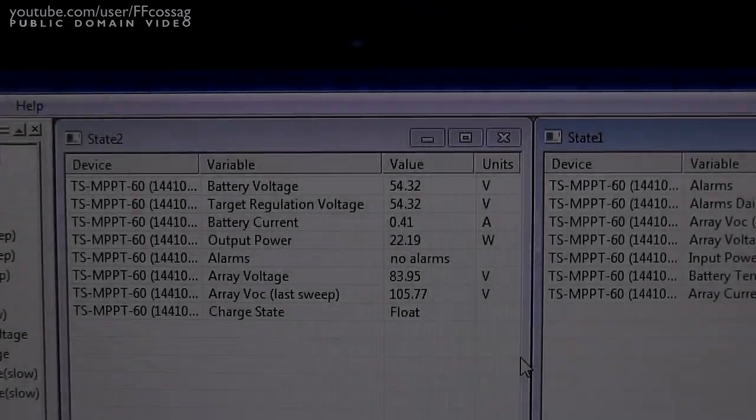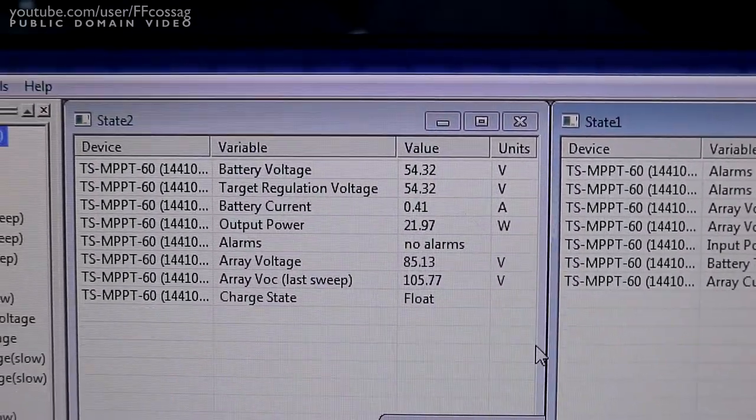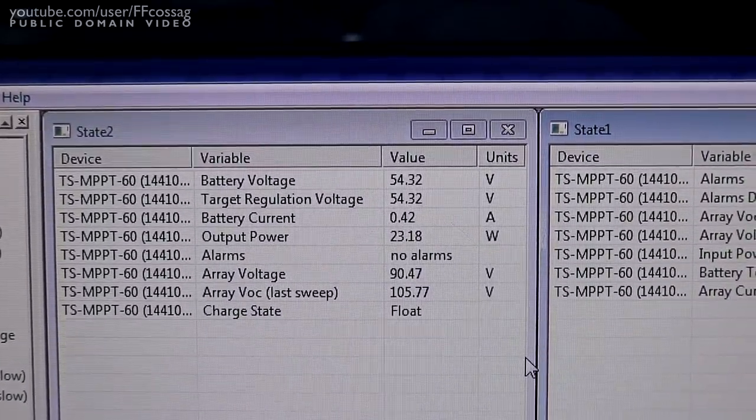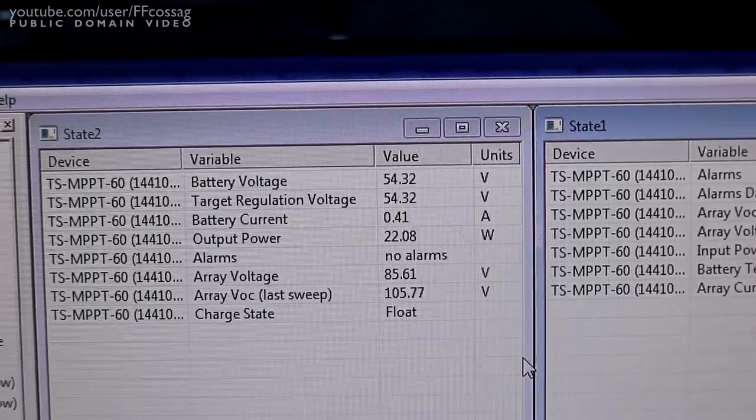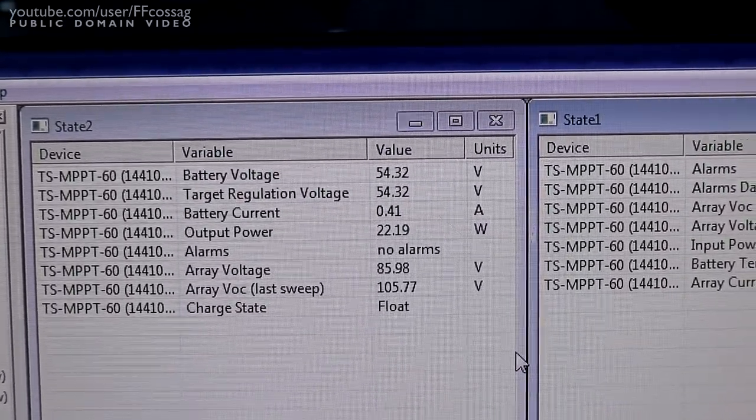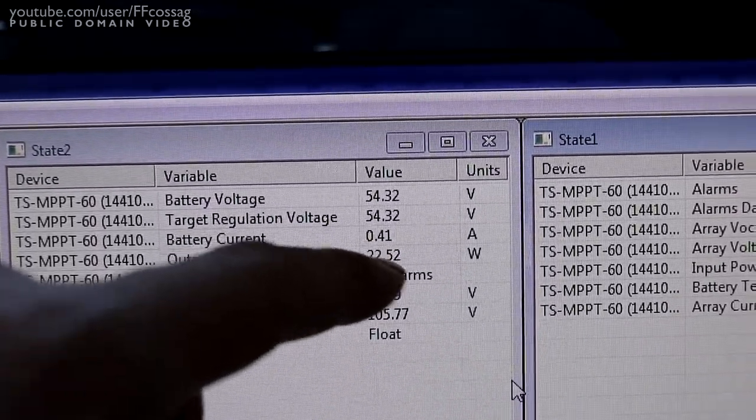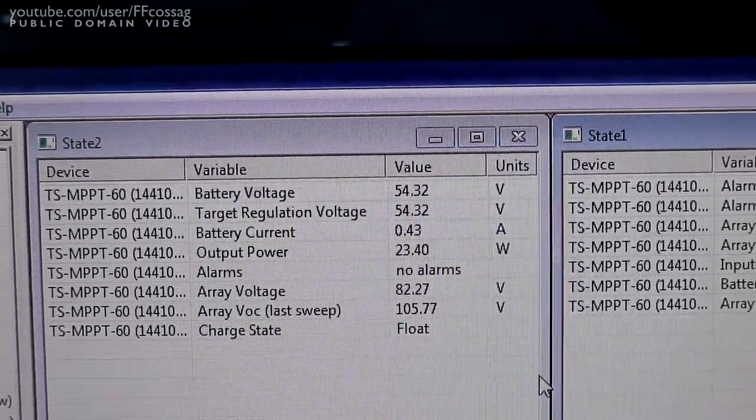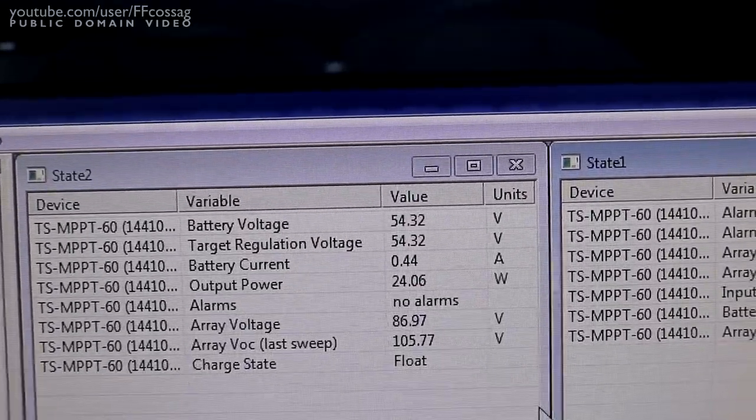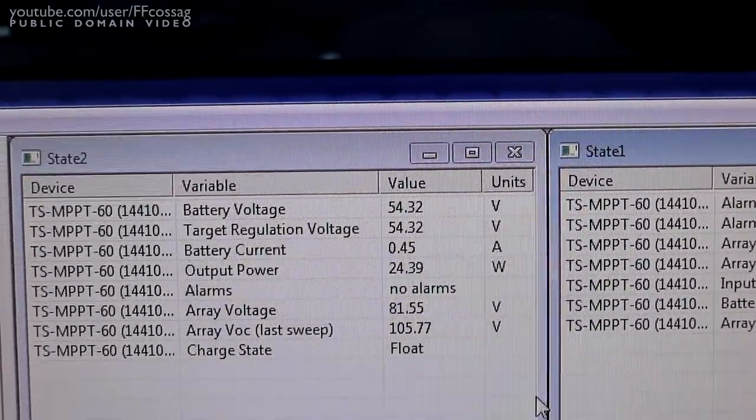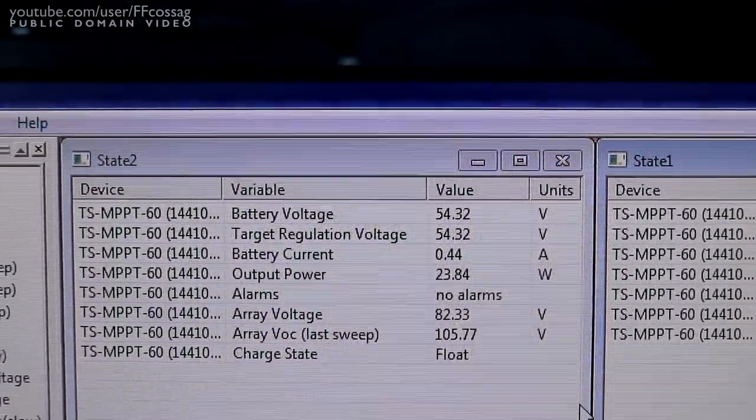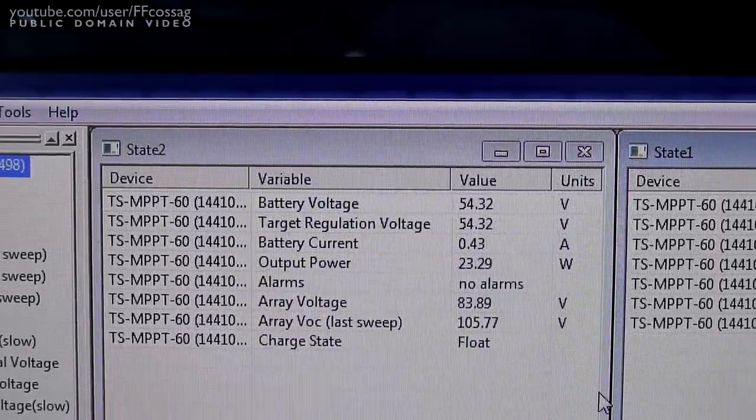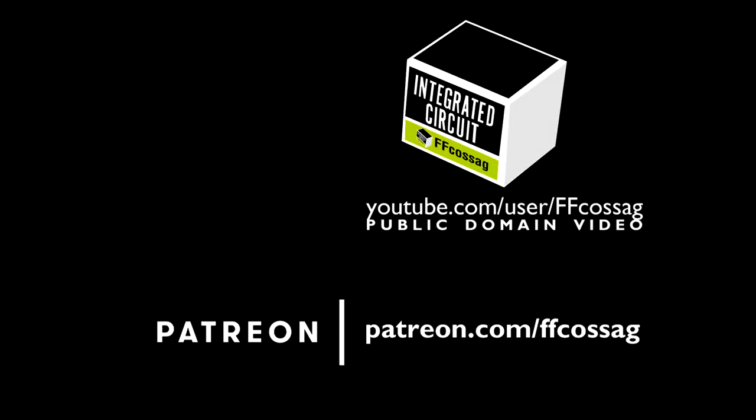Something that just keeps impressing me with these SunXtender gel cell batteries is we have 1,500 amp-hours of 10-year-old lead-acid batteries in the basement. And what's our float charge current? About 400mA. That's also about 100mA going into powering Wi-Fi hotspots. So we're talking about like 10 watts per battery bank to float charge. That's insane, especially given the age of these guys.